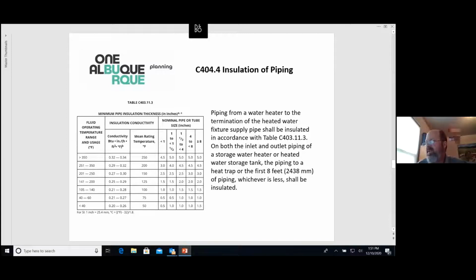So if the existing has an integral heat trap and you're putting in a storage type tank without one, you would have to pipe it in and then insulate the first 8 feet. If there's already a piped heat loop, and you're putting in a tank type water heater or storage tank that has an integral heat trap, I don't think it does any harm to have the extra piping in there. And it wouldn't need the insulation anymore. I mean, if it's already there, I wouldn't take it off. I'm not sure if that answers the question.